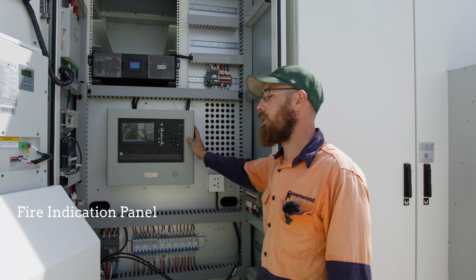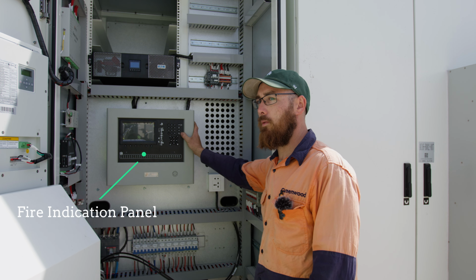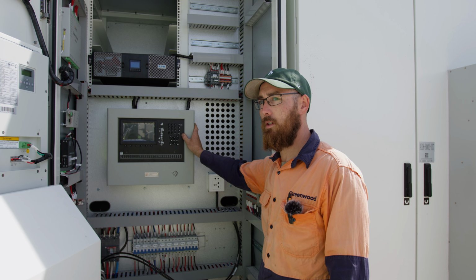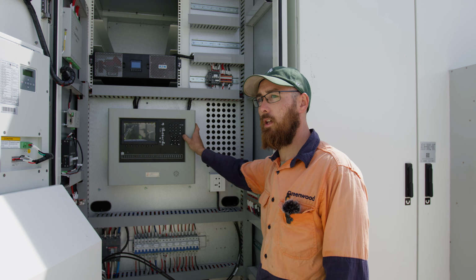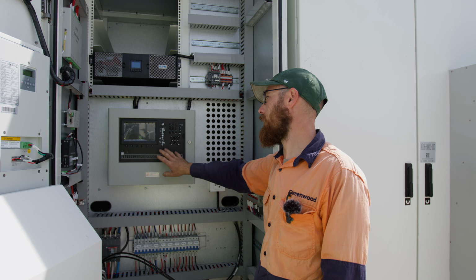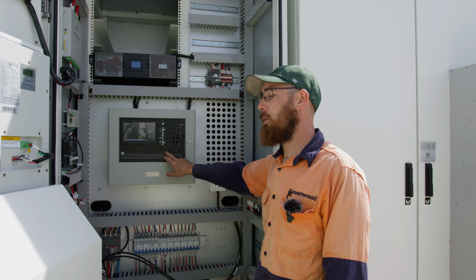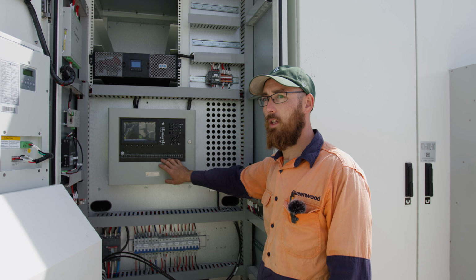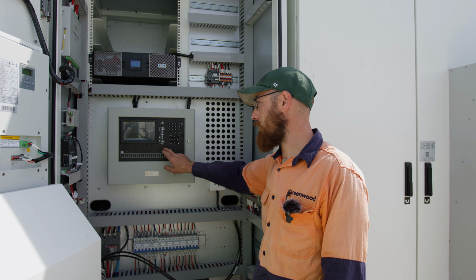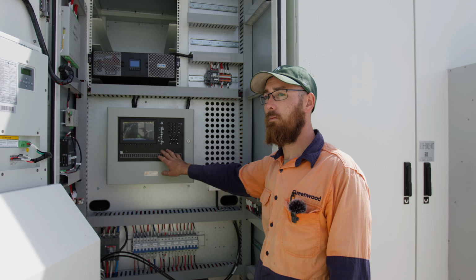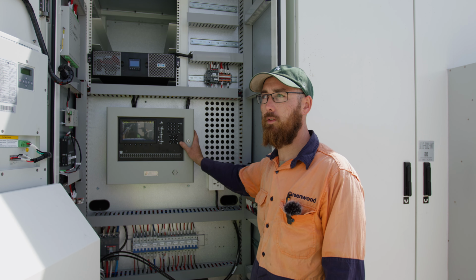And the actual LED screen or LCD screen? This here is a fire indication panel. This is connected to all of the batteries, so if there are any problems inside the batteries, they all have their own fire smoke detector and fire suppression system, which will trigger the fire indication panel. These will be interlinked to a mains fire indication panel because there are 3 of these on site, so if any of them trip, it will contact the fire brigade of the local area.